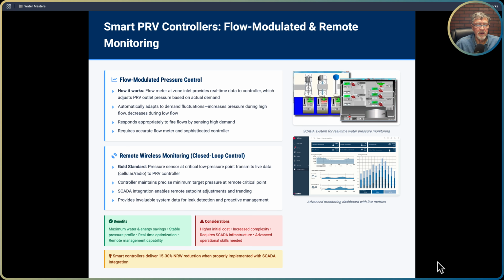So it automatically adapts to demand fluctuations, increases pressure during high flow, decreases during low flow. It responds appropriately to fire flows by sensing high demand. So if you have fire flows, a lot of these other pressure controllers, the time modulated, they can't adjust accordingly. So this can adjust to fire flows. It requires accurate flow meter and a sophisticated controller because they have to talk, and that's important.